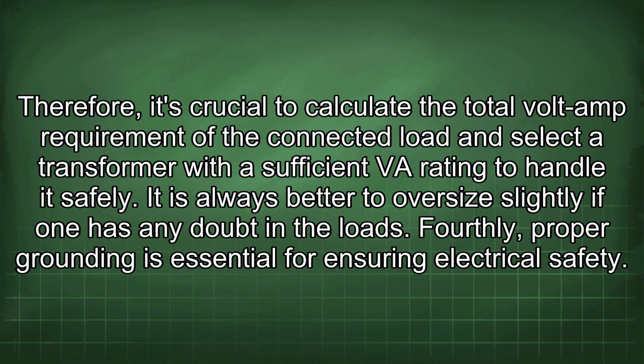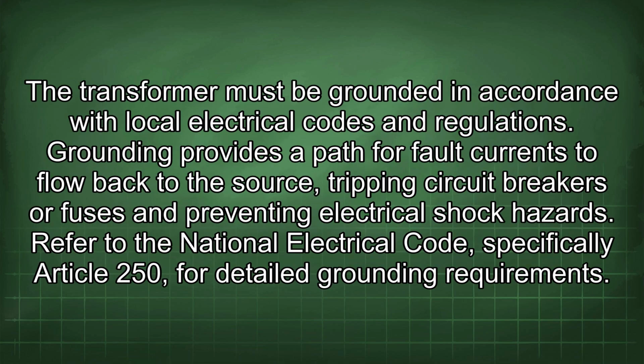Fourthly, proper grounding is essential for ensuring electrical safety. The transformer must be grounded in accordance with local electrical codes and regulations. Grounding provides a path for fault currents to flow back to the source, tripping circuit breakers or fuses and preventing electrical shock hazards. Refer to the National Electrical Code, specifically Article 250, for detailed grounding requirements.